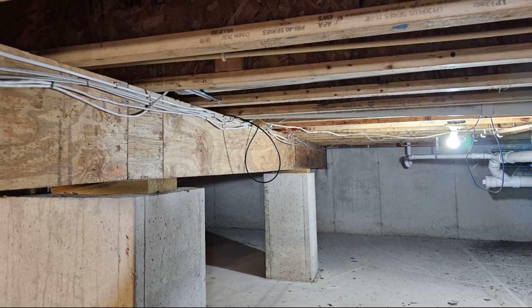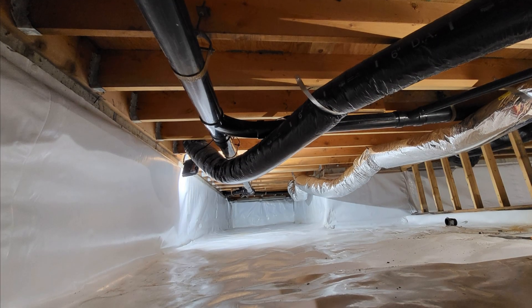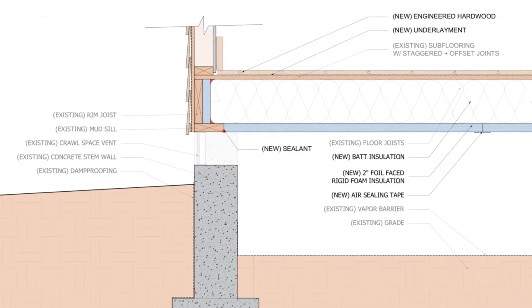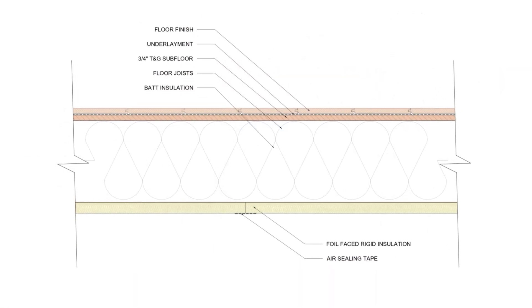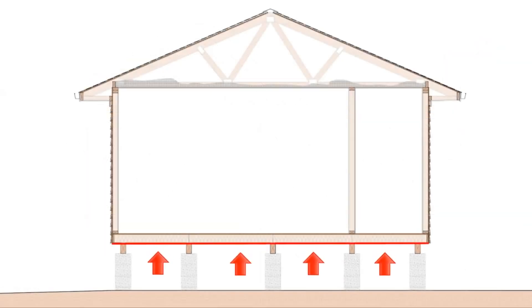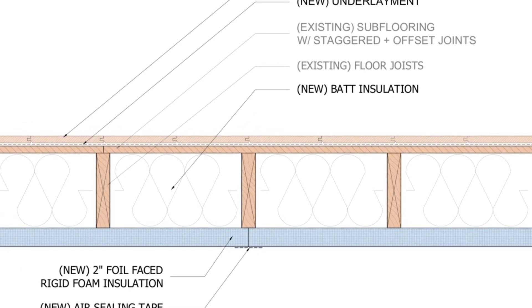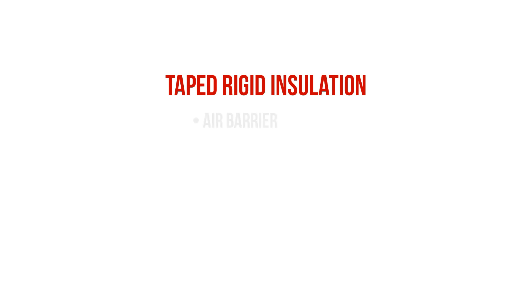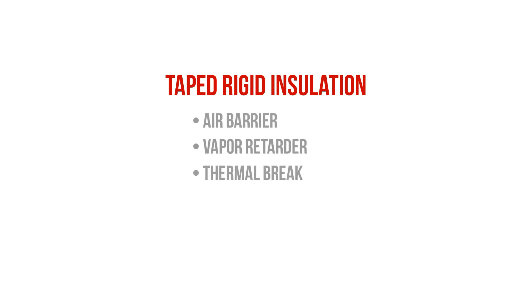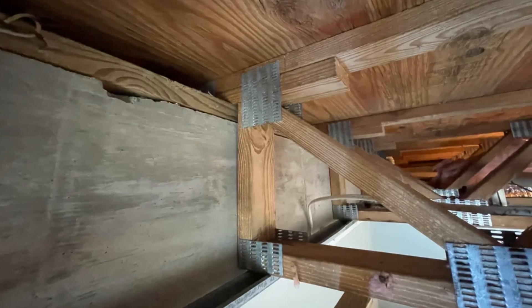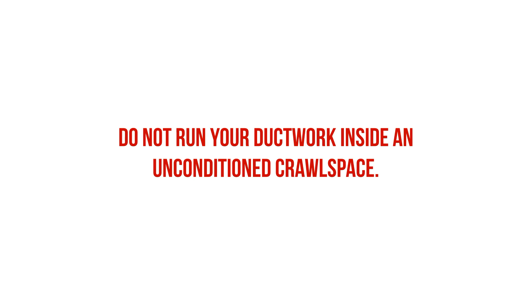We want to condition our crawl spaces so that they're insulated, air-sealed, and waterproofed, so that they're part of the interior shell and receiving conditioned air just like a basement. If we have to have a vented crawl space, we want to make sure that we're completely uncoupling the floor system from the crawl space with an air barrier so that we don't get moisture-laden air migrating up into the floor assembly. Typically we accomplish this by using foil-faced rigid insulation with taped or sealed joints, which provides the benefits of an air barrier, a vapor retarder, and will help to bolster the thermal resistance of the floor system. You also need to make sure that the ductwork and HVAC system is completely located within the conditioned space — you cannot run your ductwork in an unconditioned crawl space.